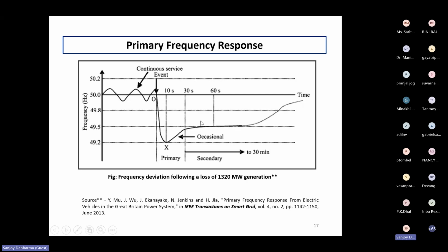To mitigate the steady state error, AGC has to come into account, where the main intention is to update the set point of the governor, which in all power systems of the world is updated every 4 to 5 seconds. This is how the frequency of the grid can be maintained.